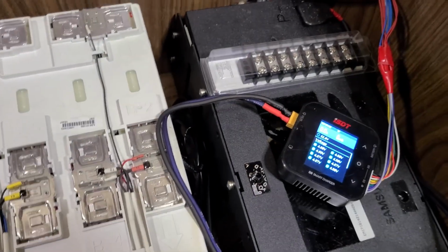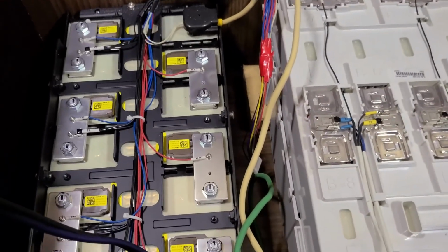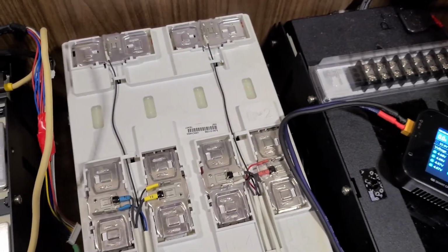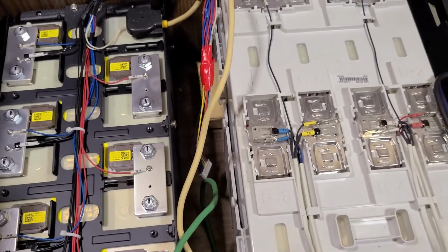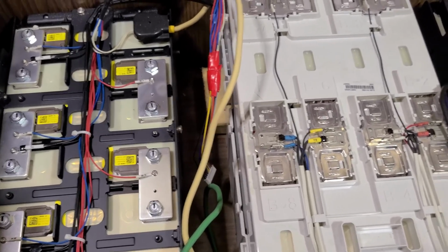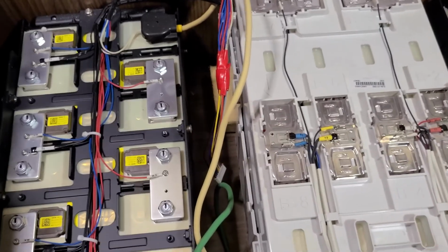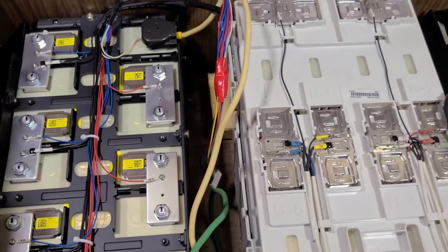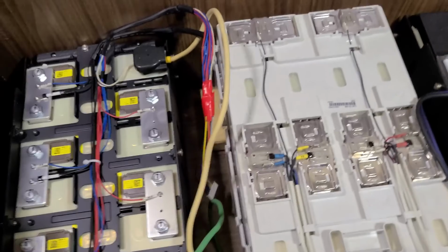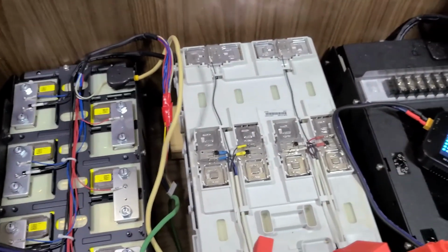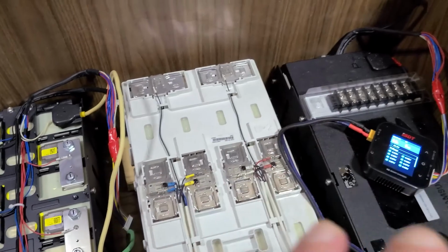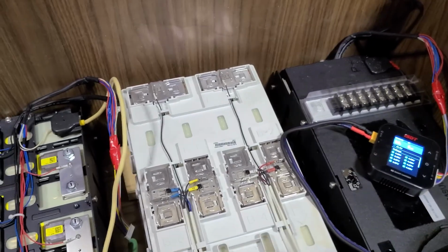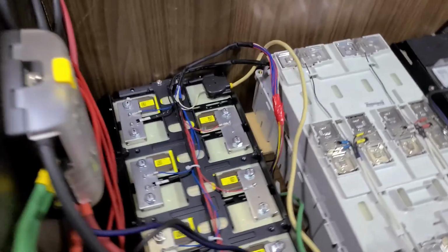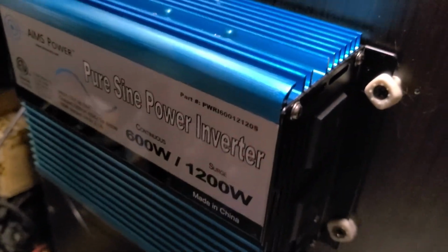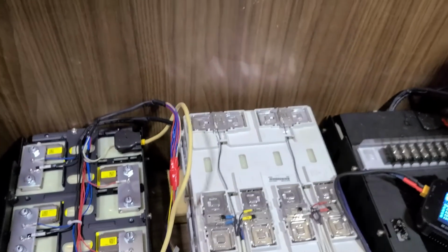And then I hear people say, well, you need a separate BMS for each battery pack. Well, to me that makes no sense, since it's one big battery. There's about, if I remember right, when I did the drawdown on this and checked it, around 6 kilowatt hours worth of battery sitting right here. And that's all I need. Really, I don't even need 6, but for the situation I'm doing here, it's perfect. Off to the side, right here, I got a 12 volt power inverter that runs off this system.